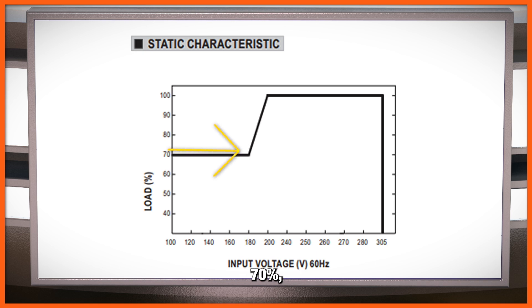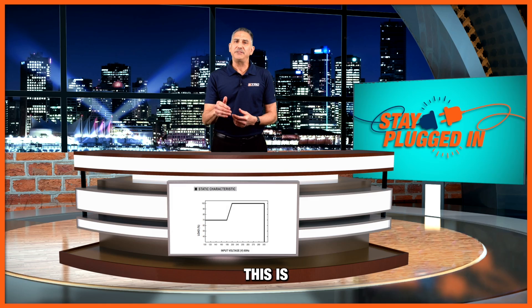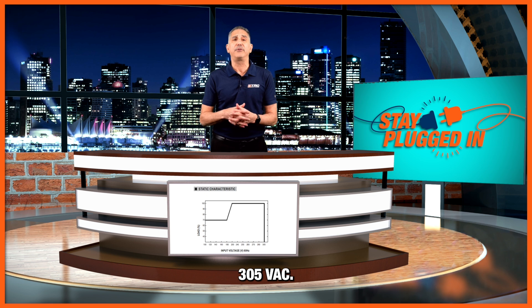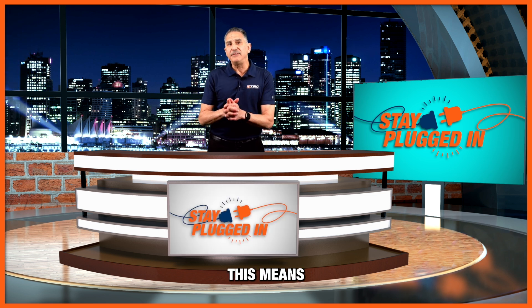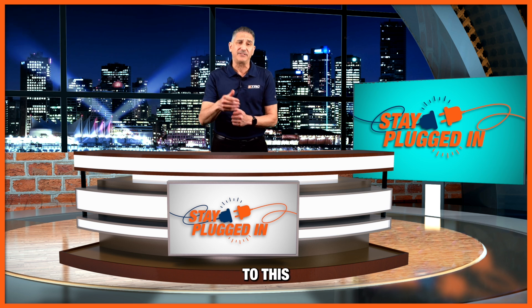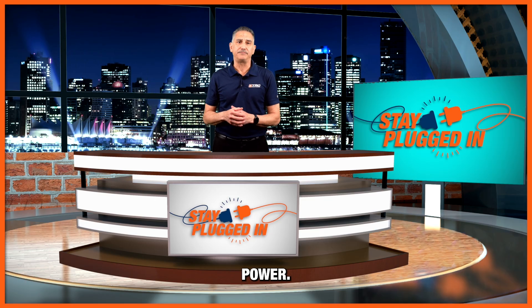This graph also shows that the 70% derating is recommended up until your input voltage is above 180 volts AC. At that point, the graph goes sharply up until you can see that above 200 volts, the full power can be delivered by that power supply, all the way up to the maximum input voltage of 305 volts AC. This means that at the rather common input voltage of 230 to 240 volts AC — which we refer to as high line — you can safely operate the power supply at 100% of the output power.